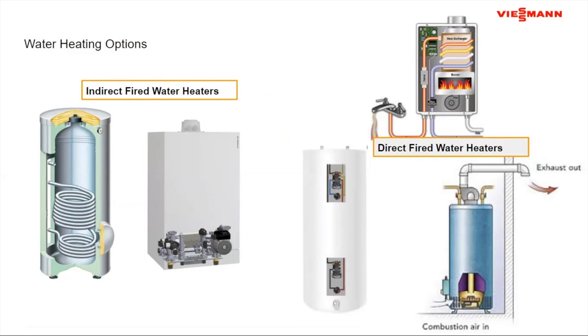You could throw out advantages, anything from overall best utilization of the heating system boiler. You know, I paid for this boiler, let's run it for 12 months a year rather than 6 months a year. I operate the boiler through the middle of summer, that way when I get into the heating season, I don't have to worry about starting up this boiler that hasn't operated for 6 months and maybe it won't start up. It could be a discussion about both of these methods being hooked to a condensing boiler, the high efficiency. It could be the fact that my local utility is incentivizing this style of water heater. It could be that from an aesthetic standpoint, if I couple the water heating into the boiler plant, there's only one exhaust going outside of the building. There's probably another half a dozen other ones that could also be utilized.